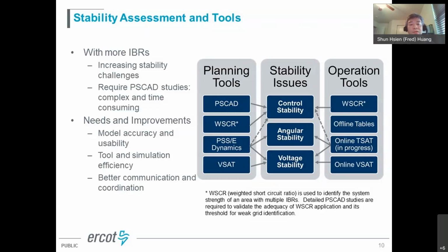Before I go to the next slides, one caveat I want to share with the group: the index in terms of SCR or any other index like WSCR we use in ERCOT - when we decided to use WSCR, we ran a lot of PSCAD studies just to make sure the WSCR index could be properly applied to a particular region like Panhandle. Our observation was that the WSCR and threshold are likely not applicable to any other region until you do the detailed analysis. So that's something we also have a challenge to try to see - can we have a universal or potentially good index that can be applied system-wide - and that's something we're working on right now.